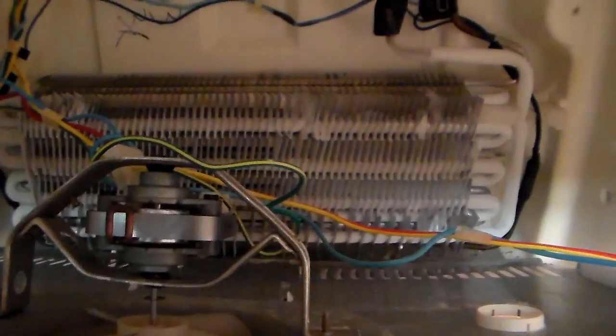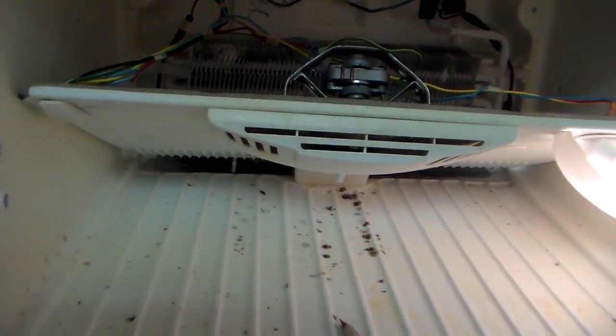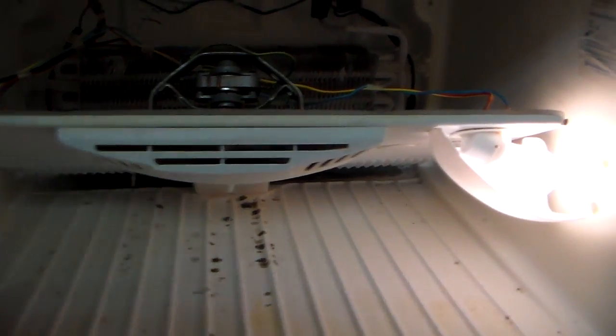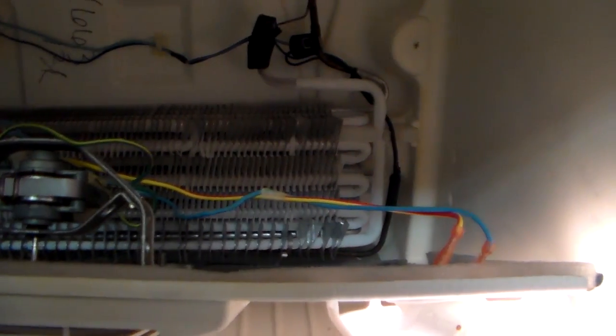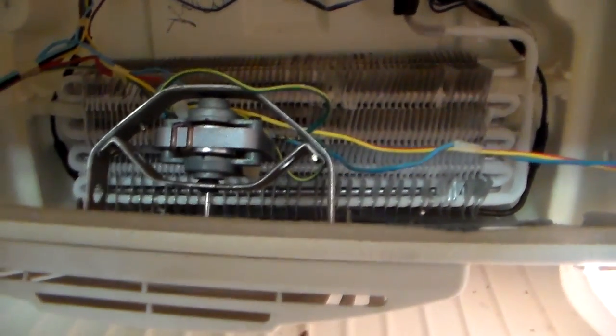You're going to wait a few minutes and we're going to see if that heater comes on. When this thing is frosted over, you manually stick that in defrost and that heater comes on, you have a bad defrost timer. No question about it.